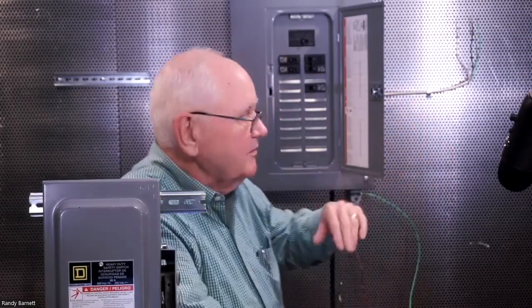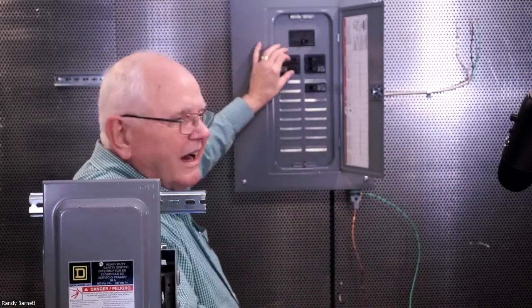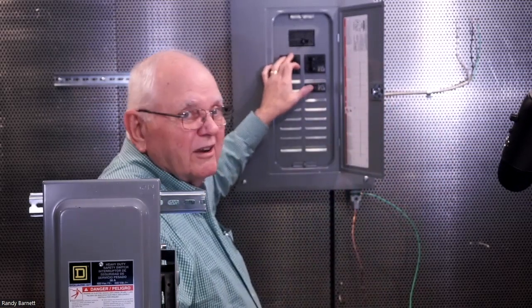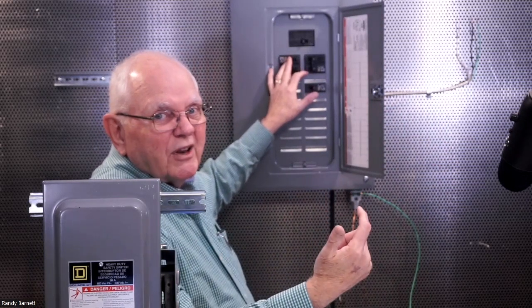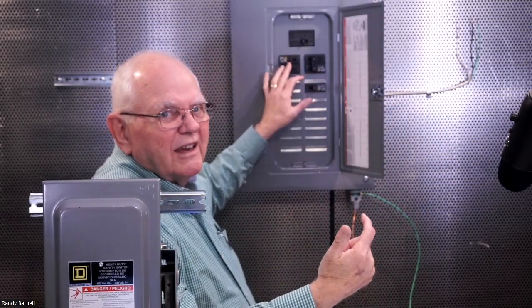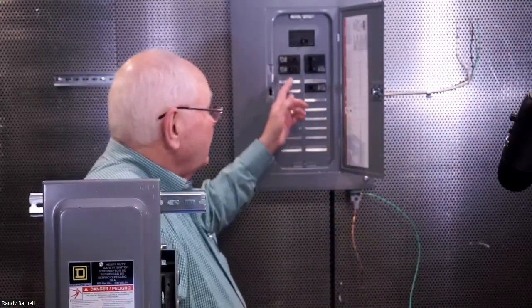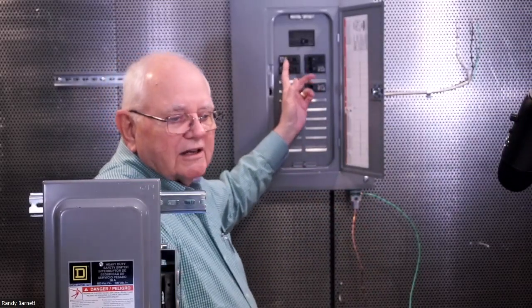Now, the thing is that if I connect the red wire to the top half and the black to the bottom half of that receptacle, or duplex, whatever, I could de-energize one and not the other one. So as a disconnecting means, that could be very unsafe. If I were just to shut off the one circuit breaker, go in there and pull the receptacle out of the box to work on something, I would still have one ungrounded conductor coming into it. And of course, that could be bad news for me. So I'm required to tie those handles together. I've got to tie them together.